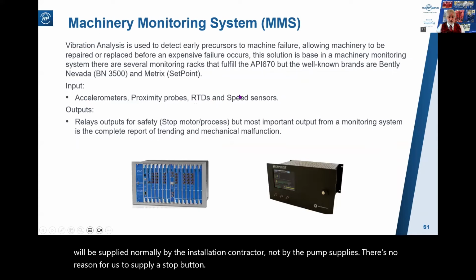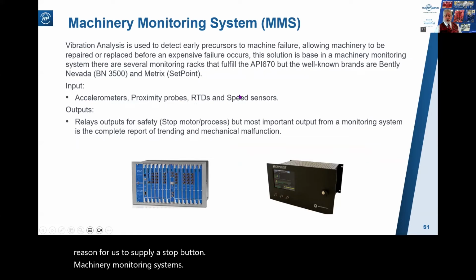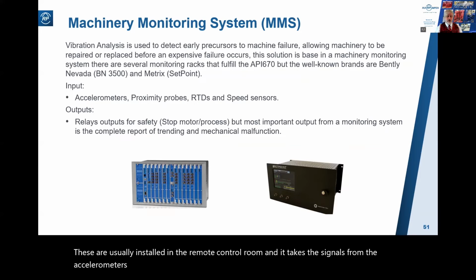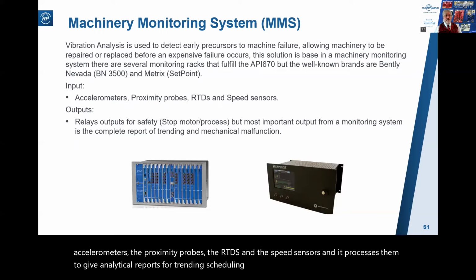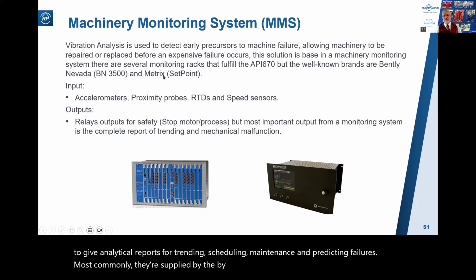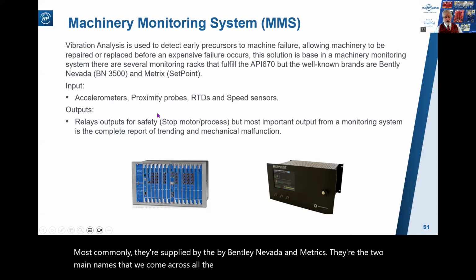Machinery monitoring systems. These are usually installed in the remote control room, and it takes the signals from the accelerometers, the proximity probes, the RTDs, and the speed sensors, and it processes them to give analytical reports for trending, scheduling maintenance, and predicting failures. Most commonly, they're supplied by Bently Nevada and Metrics. They're the two main names that we come across all the time. There are, of course, others out there.